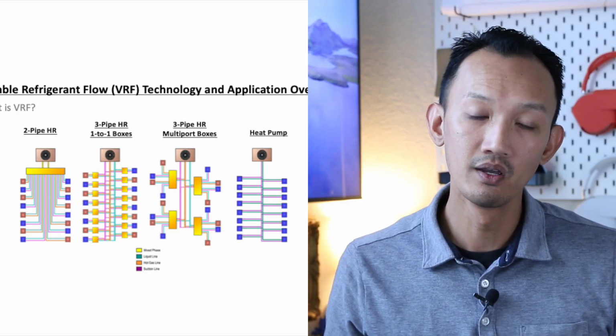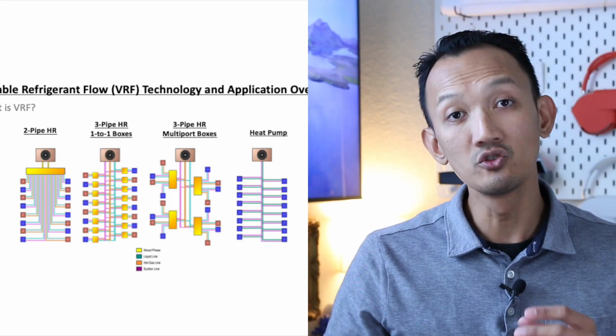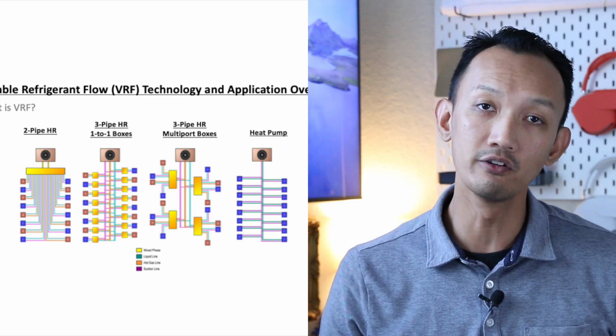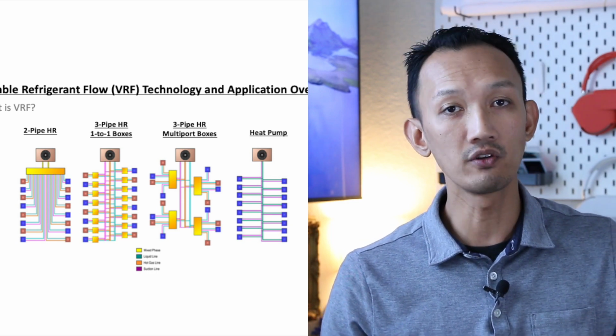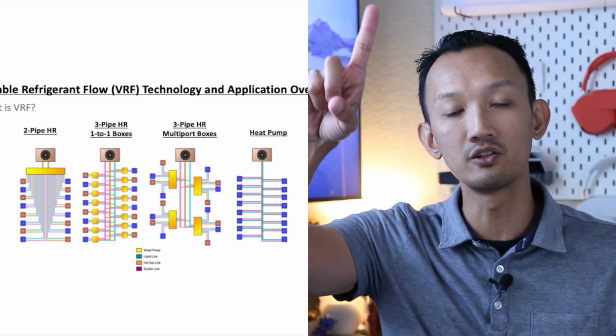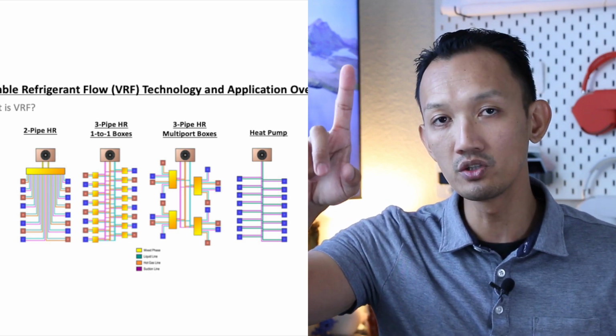And as you can see with the different types of technology, the amount of refrigerant piping needed depends on the type of system. So if you look at a two-pipe heat recovery system, you can see that there's a lot of refrigerant piping as you have to go from each fan coil back to the central multi-port distribution controller.